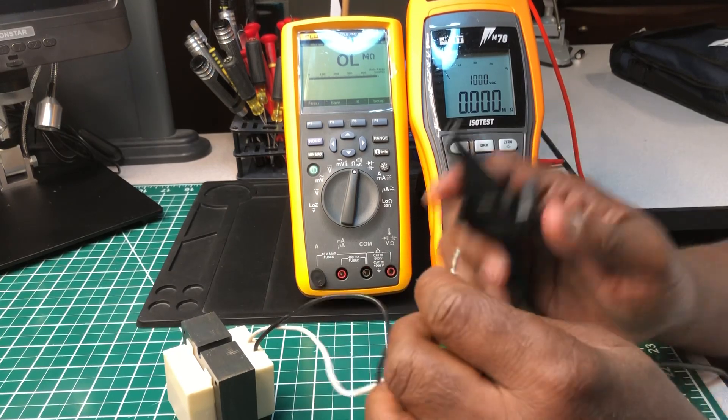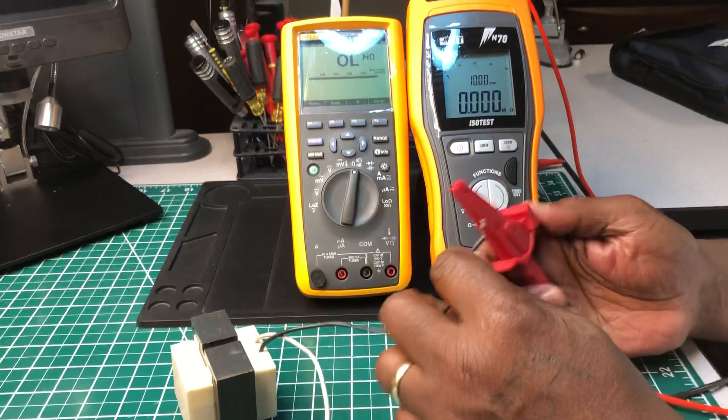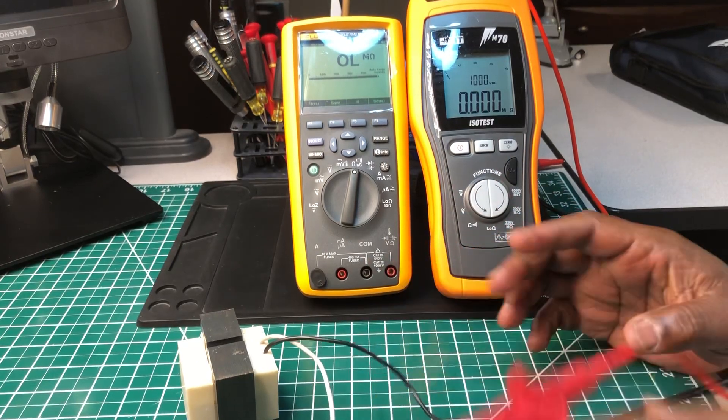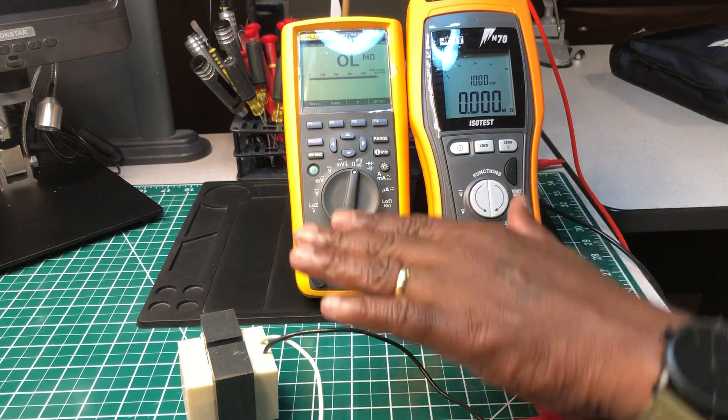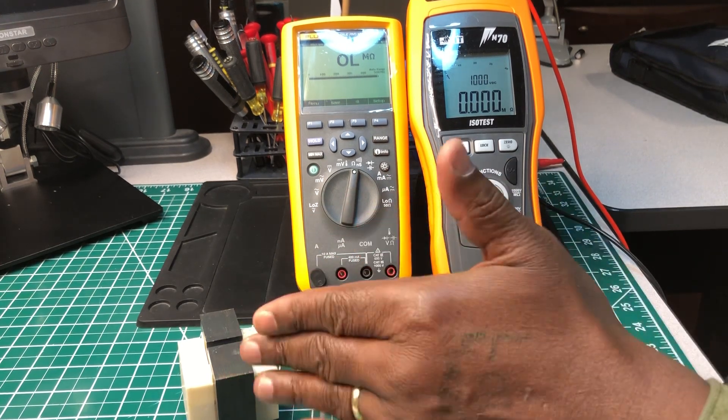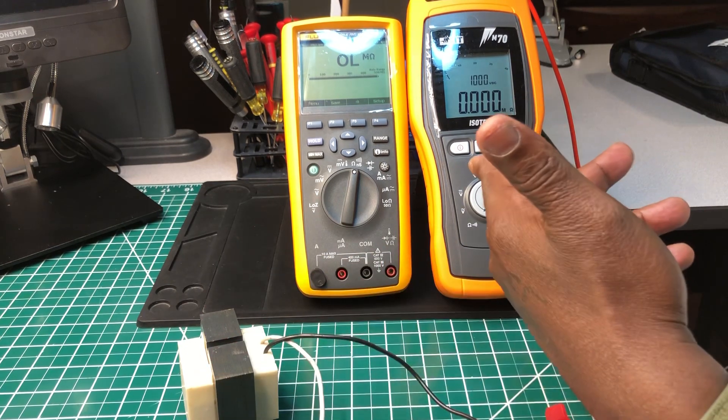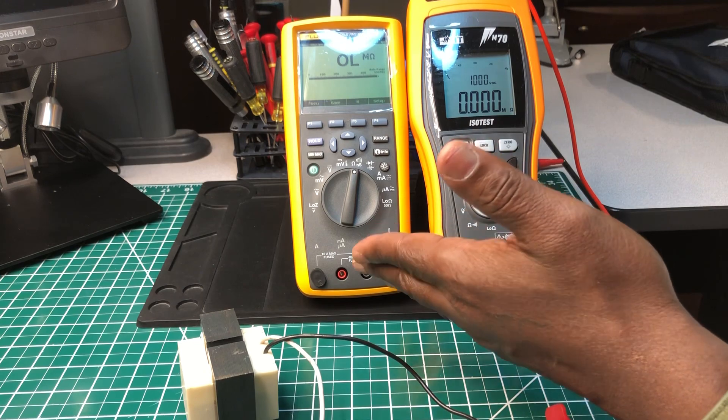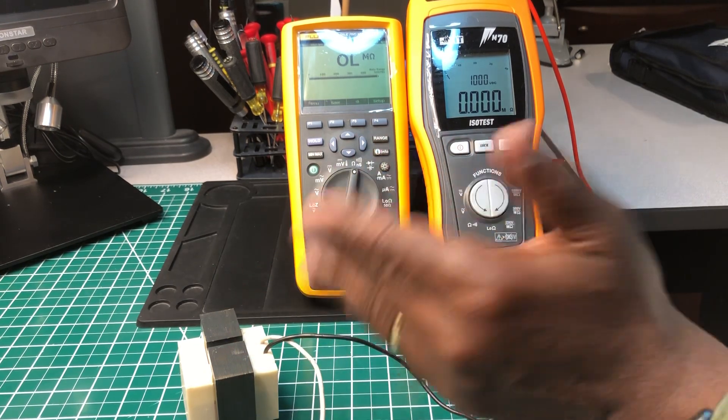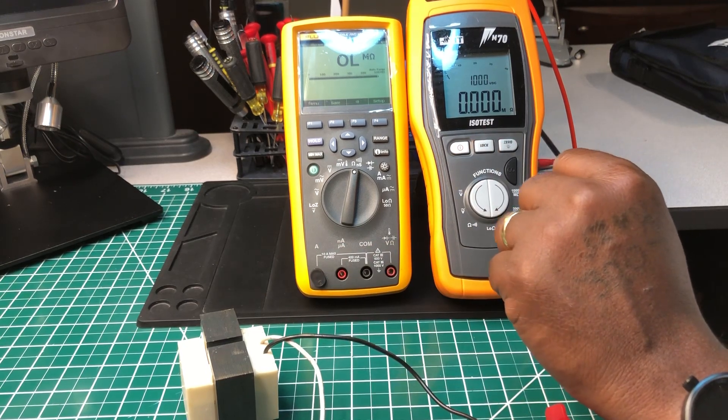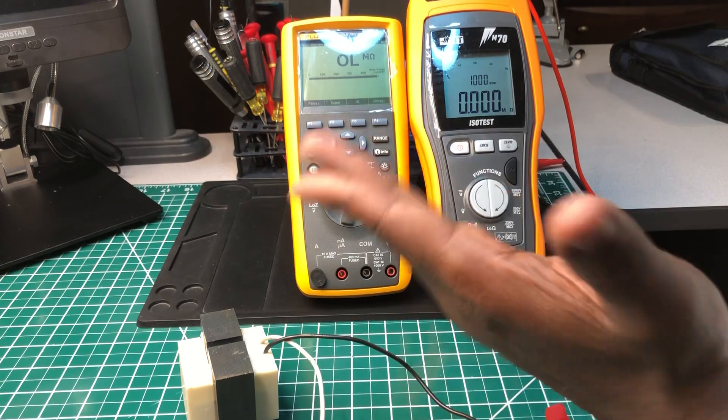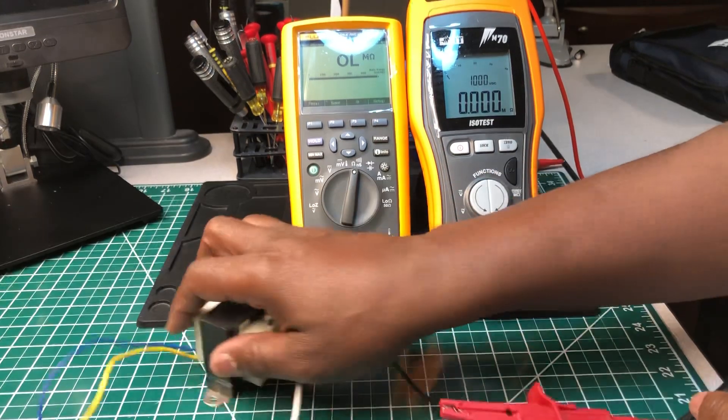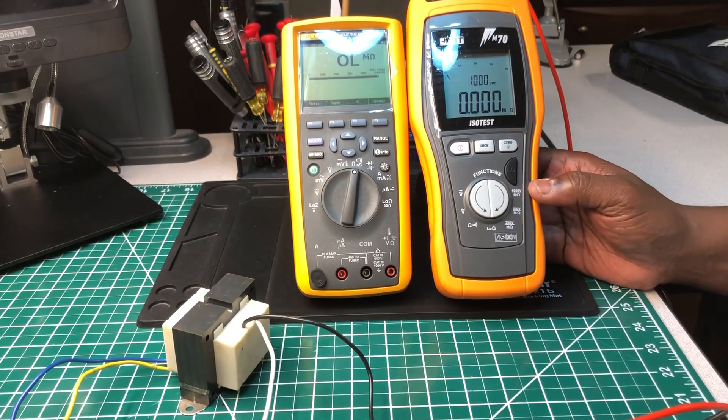Let's say you want to remove all doubt that this transformer is bad. Normally it's 120 volts, you want to double that - set your insulation tester up to 250, but you could do 500 also. But I want to go a step further than that. I want to make sure this transformer is good to remove all doubt from my mind.